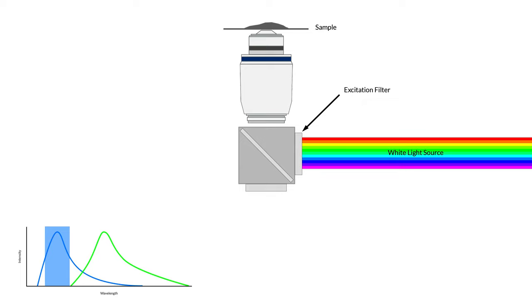In this example, the excitation filter passes between 470 and 490 nanometers. Once this excitation range passes into the filter cube, it strikes a dichroic mirror. A dichroic is a flat piece of plate glass, angled at 45 degrees, that has special coatings on it that reflect wavelengths of light shorter than some designed cutoff wavelength, and transmits wavelengths longer than this cutoff.